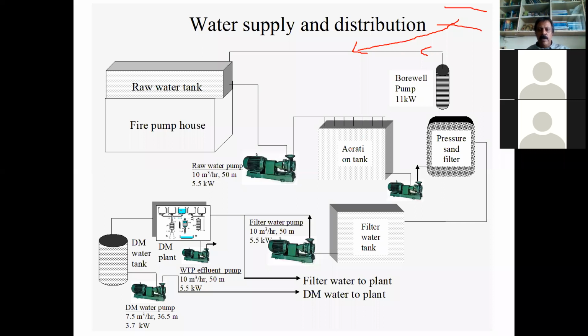So the first question: why aeration? Why is this required at all? When you have changed the source of the water from river to bore well, this aeration process itself is not required. Now this water is again pumped to a pressure sand filter. The pressure sand filter filters all the suspended particles, then it goes into a filter water tank. From the filter water tank, it is taken for further treatment for DM water. So we have two sources of supply: filter water and DM water. And as we measured, the total suspended solids here are well below the limit. So this pressure sand filter was also not required.